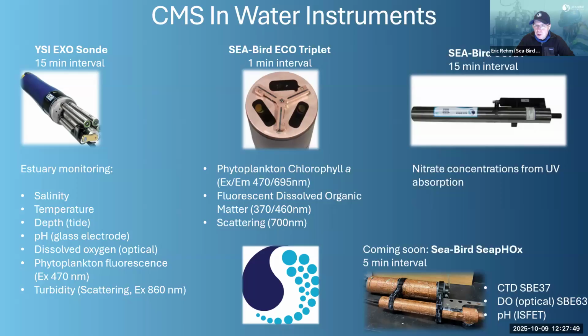There's also a SUNA, which runs less often just due to the cost of the lamp, and probably the time scale of the measurements are not as important to sample at a high rate. So that's sampling at a 15 minute interval. The SUNA is basically an ultraviolet lamp and an ultraviolet spectrometer looking at the absorption due to both salt water, but more importantly, due to nitrate. And nitrate is resolved as a part of that.